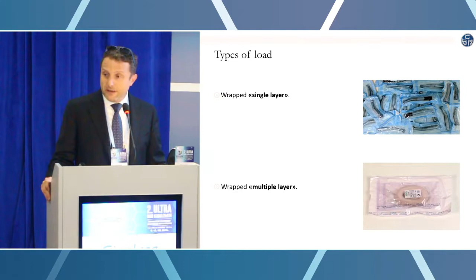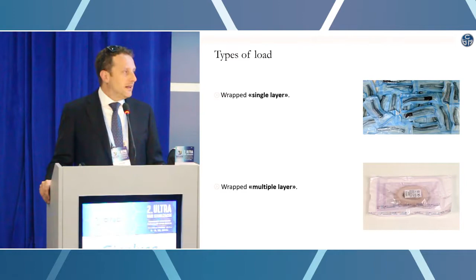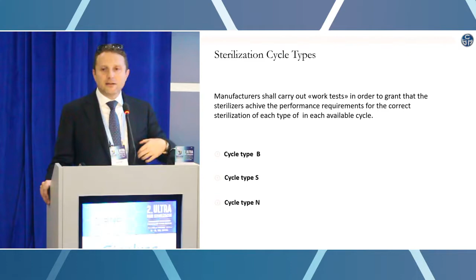Another aspect that should be considered is the single layer wrapping and the double layer or multiple layer wrapping. Why am I saying this? Because the reference norm on benchtop sterilizers states that the manufacturer should classify the cycles into 3 different levels: cycle type B, cycle type S, or cycle type N. Unfortunately, the market was a little bit confused about this definition. Sometimes we spoke about B-class, S-class or N-class sterilizers. This is wrong. The sterilizers are all the same from the technical point of view. They have to have the same requirements, but what is defined as B, S, or N are the cycles. So you may have a sterilizer with B cycle plus S or N cycles.